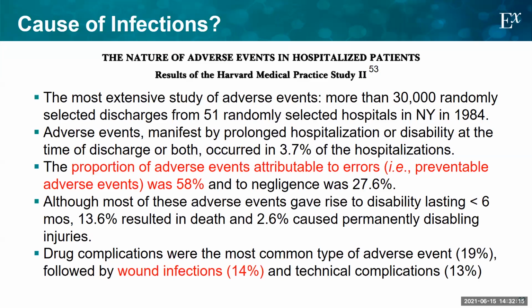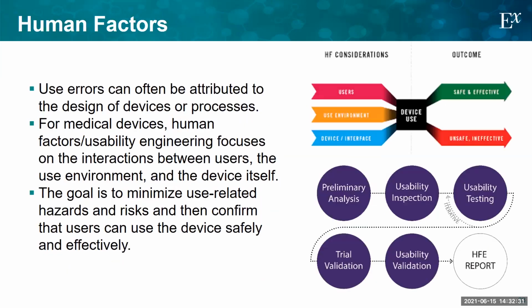So what this is suggesting is that most of the problems, over half of the problems with infection, are probably due to an error in the way the device was used or handled. And so what could we do to address that? And this brings in the role of human factors. So if we're to accept the hypothesis that use errors are often attributed to the design of the device or process itself, then for medical devices, we can use tools such as human factors and usability engineering to focus on the interactions between users, the use environment, and the device itself. So the goal, of course, is to minimize use-related hazards and risks, and then somehow measure to confirm that users can use the device safely and effectively.